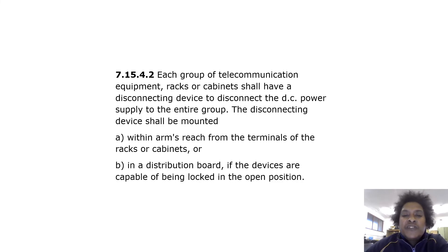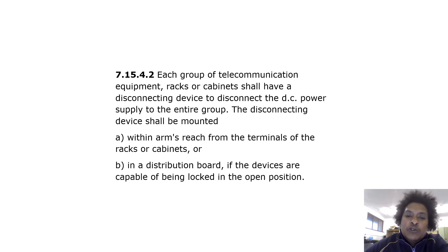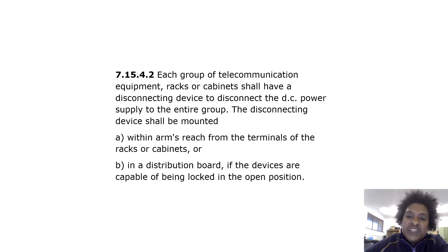Each group of telecommunication equipment racks or cabinets shall have a disconnecting device to disconnect the DC power supply to the entire group. The disconnecting device shall be mounted within arm's reach from the terminals of the racks or cabinets, or in a distribution board, if the devices are capable of being locked in the open position.